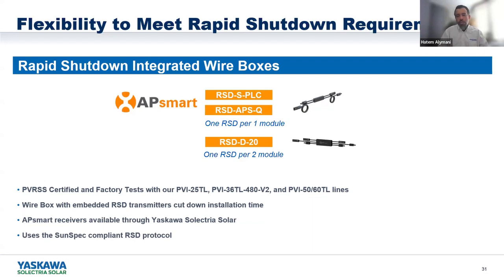As we say, the wiring box will come included with the transmitter. The transmitter is what's going to communicate with the rapid shutdown and send the signal to turn the string off or to activate the string. If you happen to have an installation where you don't need rapid shutdown devices, let's assume you have an installation for a carport, for example, or for ground mount, in that case you don't need to install rapid shutdown devices on the modules, and you still can use a wiring box with a rapid shutdown transmitter. It's not really going to affect the string. If you're not comfortable with it, you can easily disconnect the power from the wiring box, and we do have an application note on how to do that. But most of our customers don't really bother because honestly, it's not going to affect the string at all.